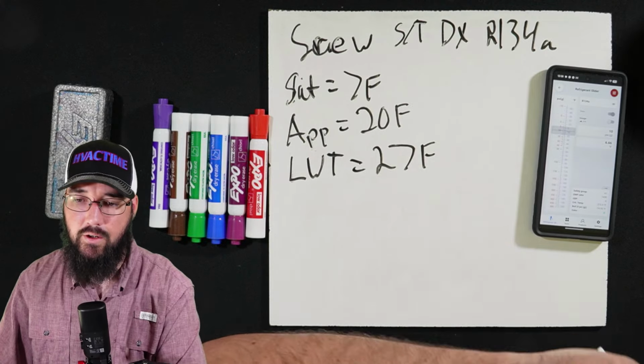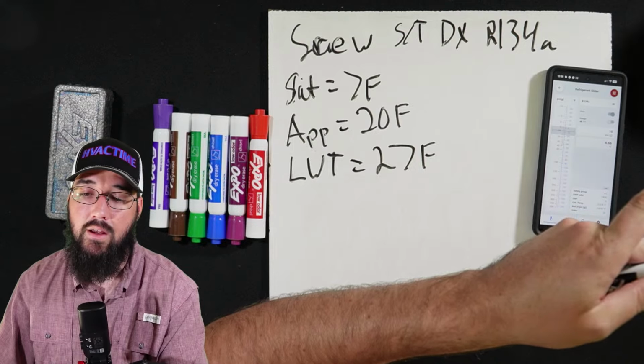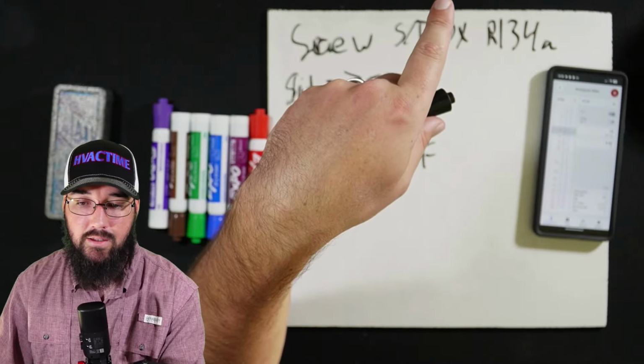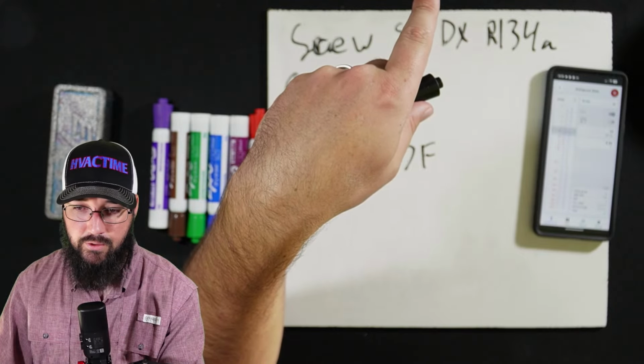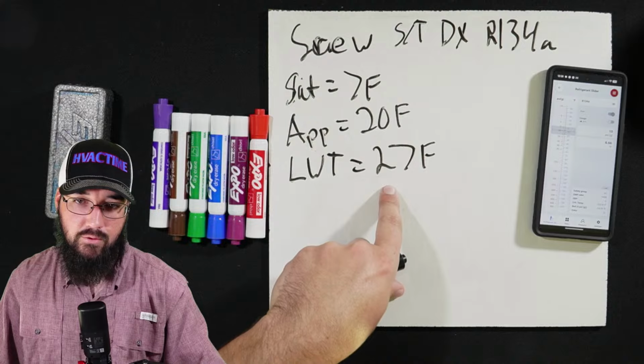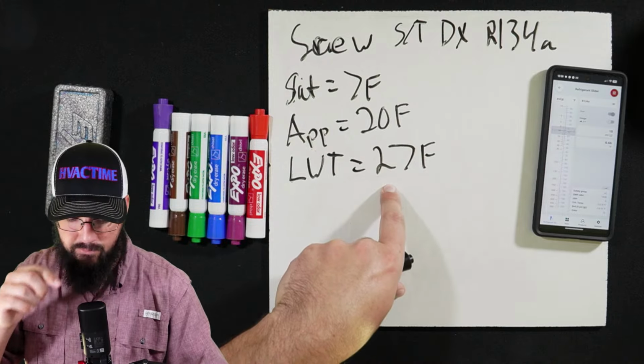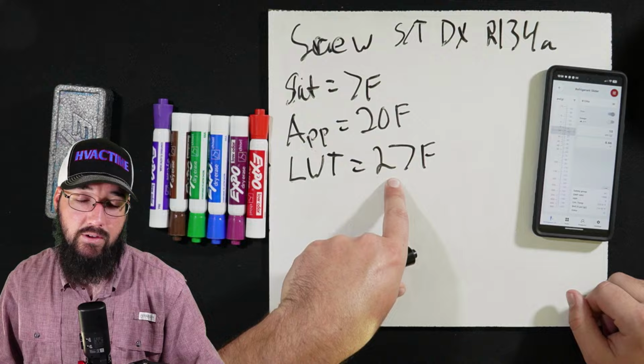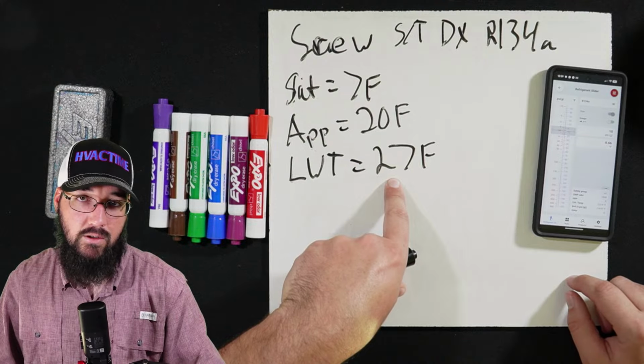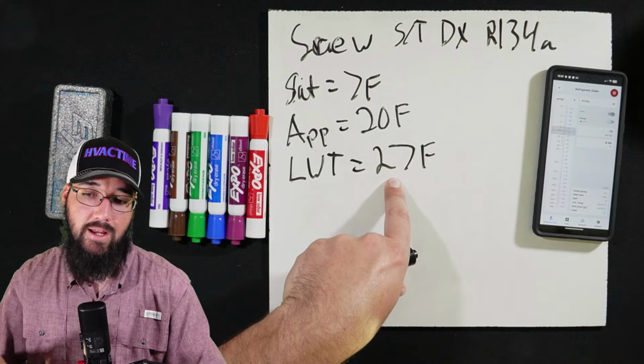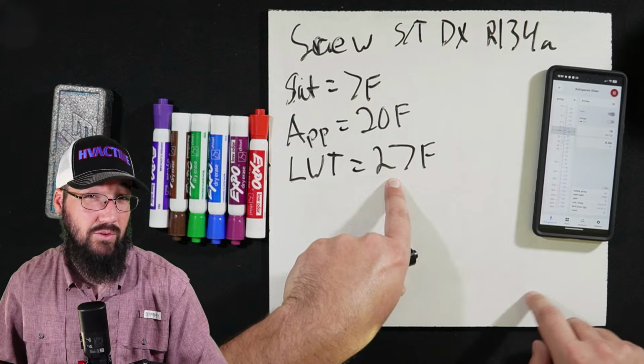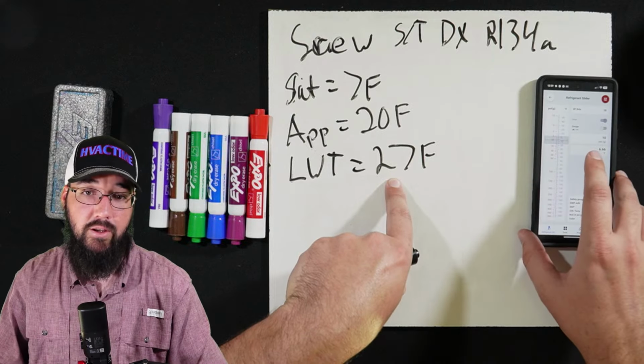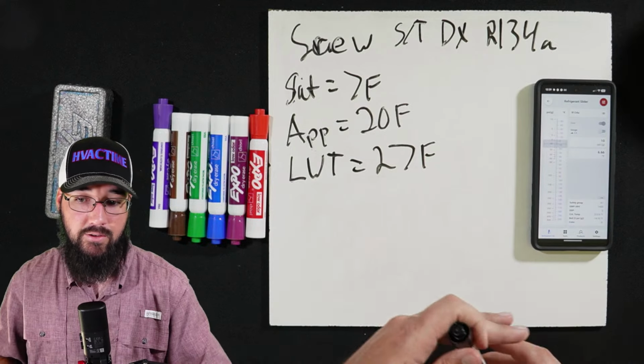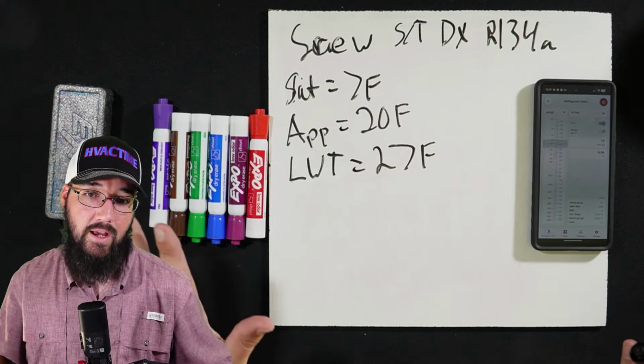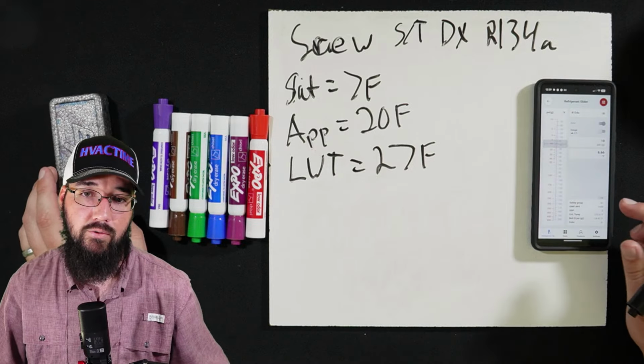Okay, so leaving water set point is 45. So are you telling me that your set point is 45, but you're actually getting down to 27 leaving? Is that true? Or are you seeing 10 psig at 45 degrees leaving? This is a really important piece of information we've got to get right. We need to be on the same page here. This completely changes how we're going to approach this troubleshoot and what we're going to do for this machine.